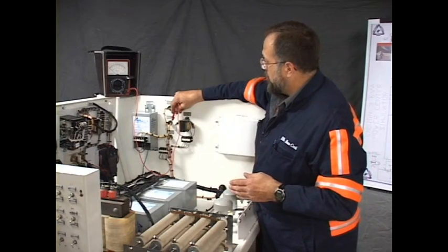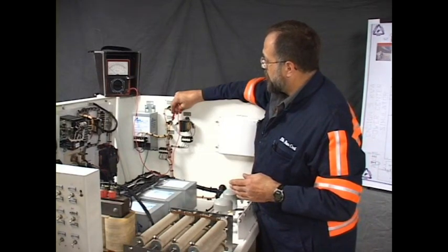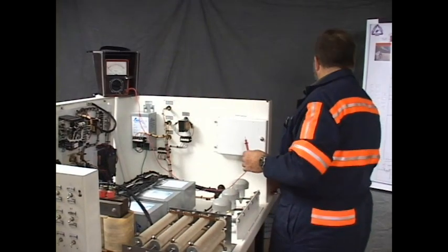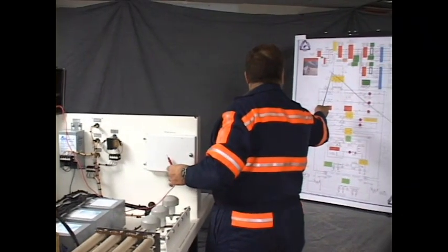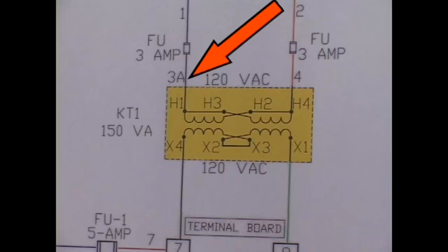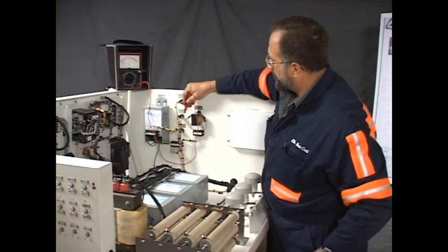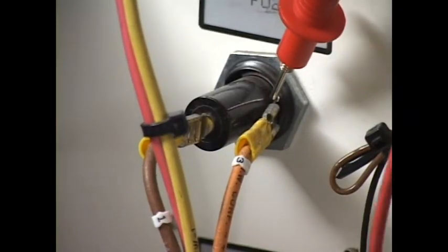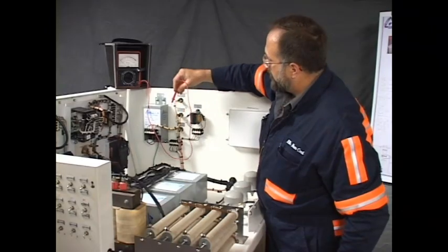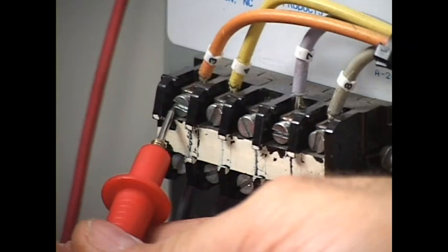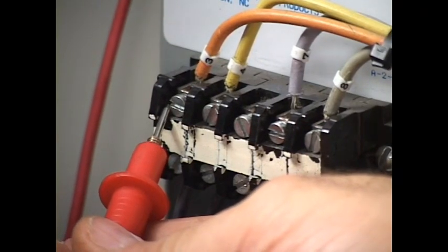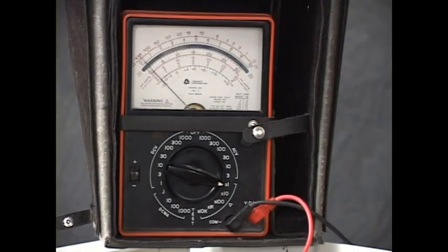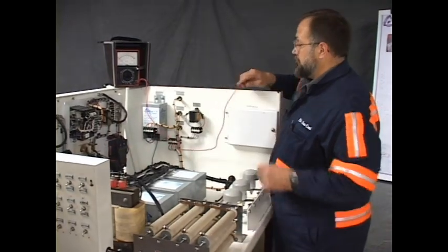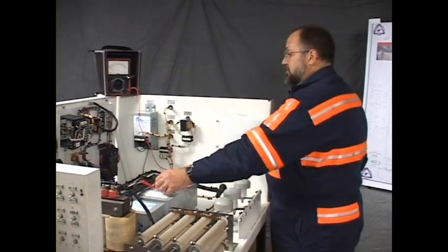Now, I'm going to proceed through the circuit and read to the other end of the wire attached to the load side of the fuse. This is wire number 3. As you can see, it goes to H1 on KT1. Wire number 3 is an orange wire. It has a wire marker of 3. I go to the other end of it on KT1, wire number 3, and I have continuity. That is as it should read.